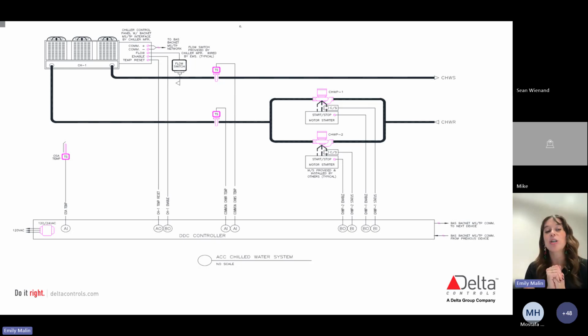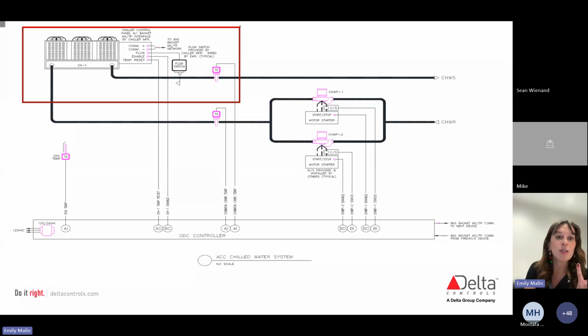And I want to give a special shout out to our friends at Sizer Co who provided me with this lovely control diagram here. But what we're going to be on the lookout for are those inputs and outputs. Let's look through the components, whose responsibility these components actually are, and start to think about, again, how we can take our zone from the actual condition that's being monitored at the zone to that desired set point condition. So from the top left here, we're going to start at the chiller itself. Most likely, and I apologize if this is hard to see, you guys, I will send this out too, and it'll be in PDF capability.